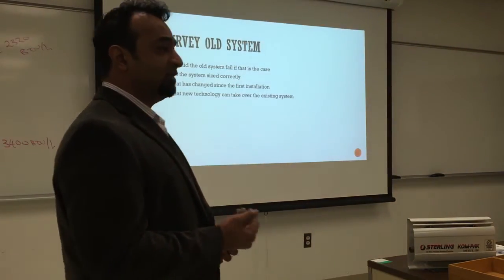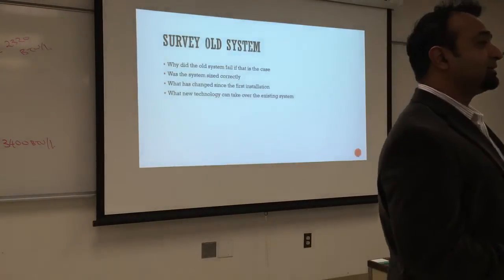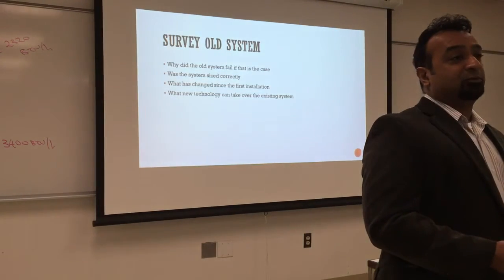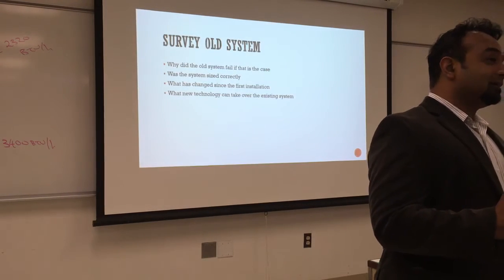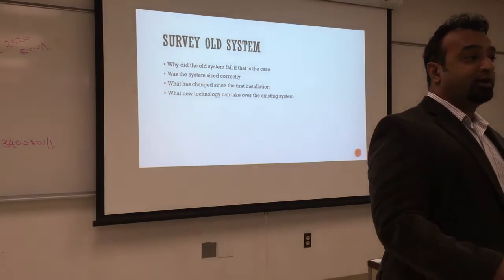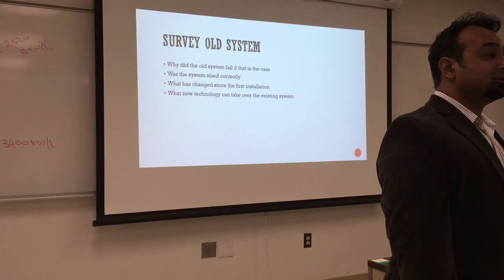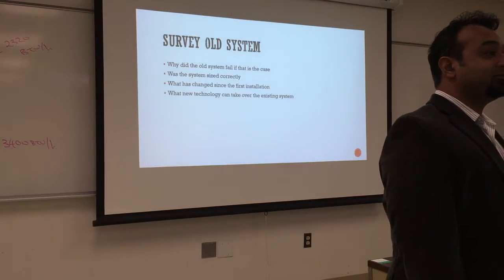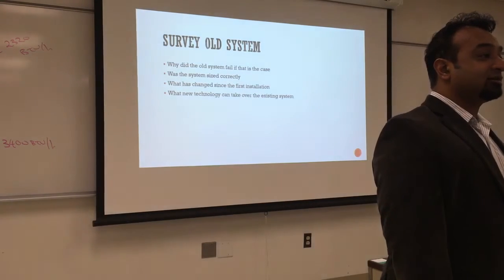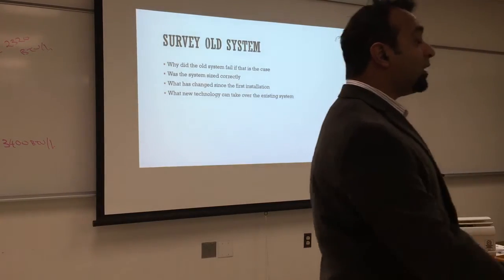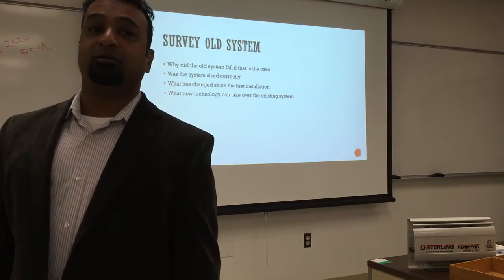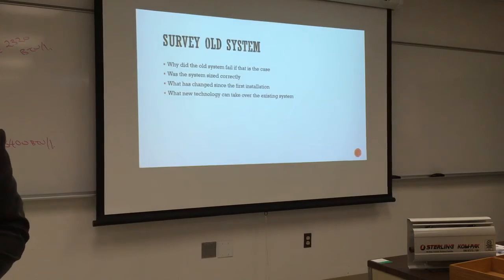Do not take the first obvious answer as the right answer. You'll learn this when we do boiler troubleshooting—you have to ask 'why' five times. Why did it fail? It rusted. Why did it rust? There's extra moisture in the vents. Why is there extra moisture? It's cracked. Why is it cracked? It's not the right clearance or thickness. You have to understand the root cause, otherwise it will happen again—and it will be blamed on your work.